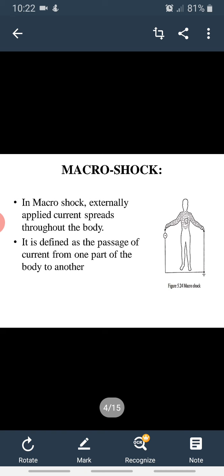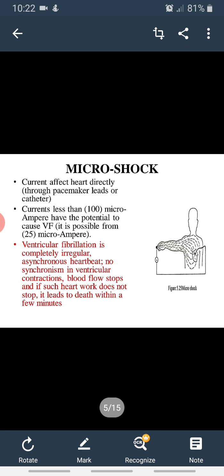In macro shock, the external applied current spreads throughout the body. It is defined as the passage of current from one part of the body to another. Next, microshock. The current affects the heart directly through pacemaker leads or catheter. A current less than 100 microampere has the potential to cause VF. VF means ventricular fibrillation. It is possible from 25 microampere. So from 25 microampere to less than 100 microamperes, we may cause ventricular fibrillation due to the shock.